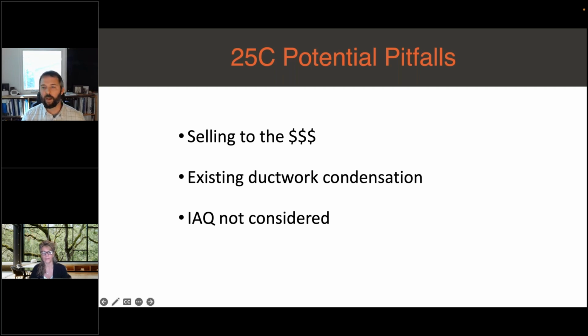Existing homes with poorly insulated ducts moving from a single-speed to a multi-speed system may run into condensation issues on colder ducts that stay cold longer. This can be worse if the ductwork wasn't sealed before and now is, since we're moving further from a slightly conditioned space, increasing the delta between air in the ducts and outside, which can lead to condensation.